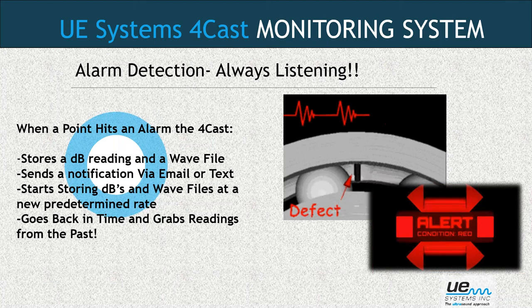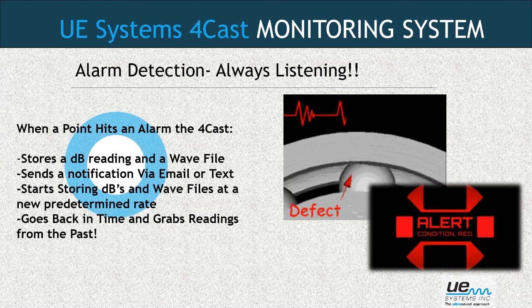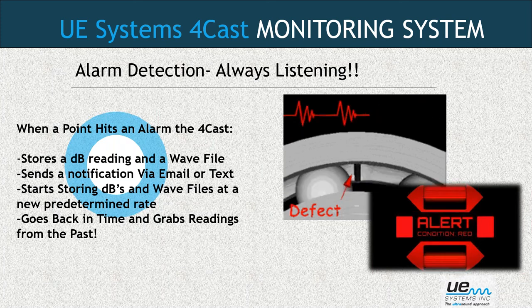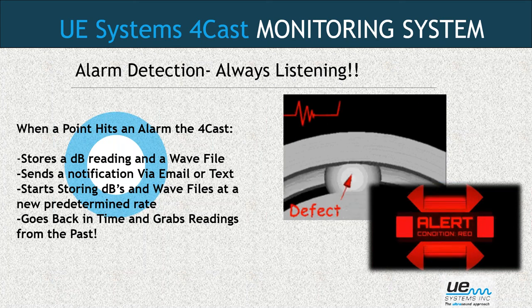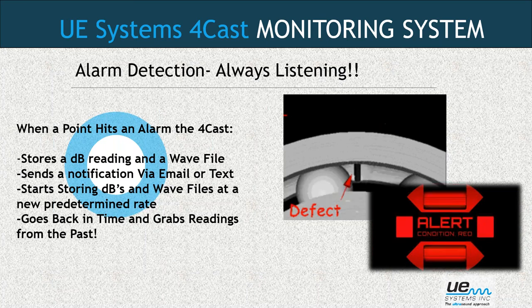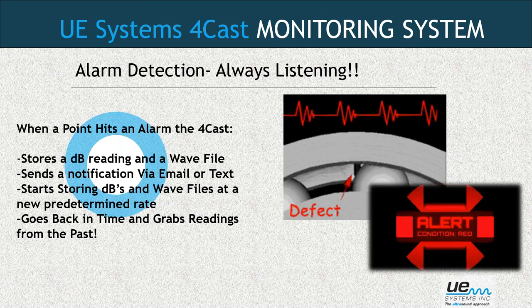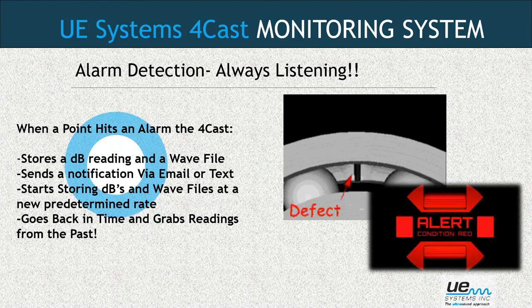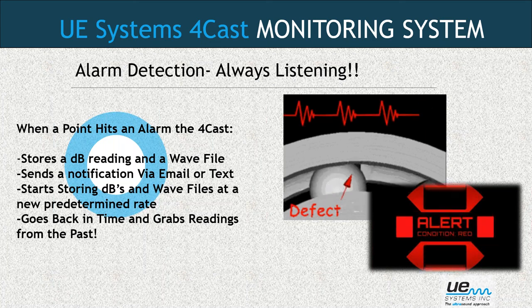The last thing it does is it goes back in time and it'll grab readings from before that alarm even took place. So from a root cause analysis standpoint, it gives us the ability to go back and see, did this particular point slowly increase? Did the dBs go up over the course of a week? Or was it running fine and the dBs went up the day before it alarmed or hours before it alarmed? So again, it's almost like the video camera in the convenience store. Once it gets robbed, you can rewind the tape and see what happened leading up to the robbery. You can see the guy casing the joint 2 days before.